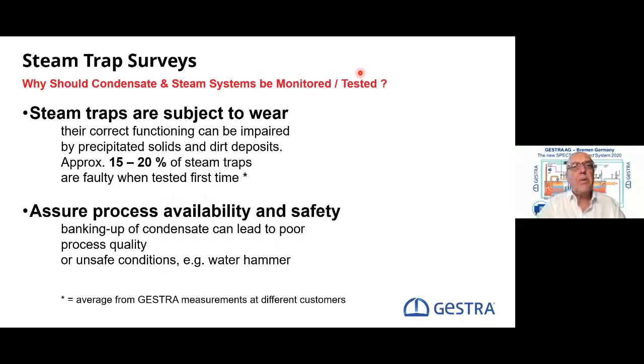And of course, we also make a survey not only for steam loss, but also for banking up. We measure the temperatures in the steam trap, and when we find out that it's not a temperature close to the saturation temperature in this customer field, then we also find out that the banking up of condensate can lead to poor process quality, unsafe conditions, water hammer. So we also test the right steam trap for banking up and so on.